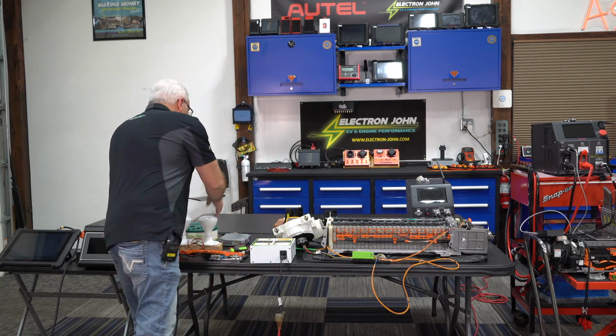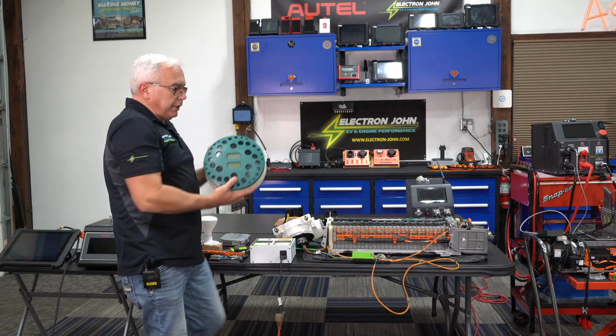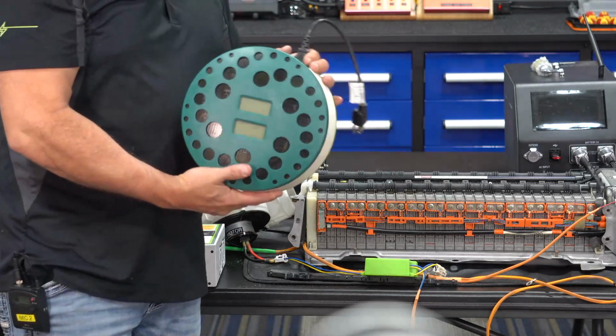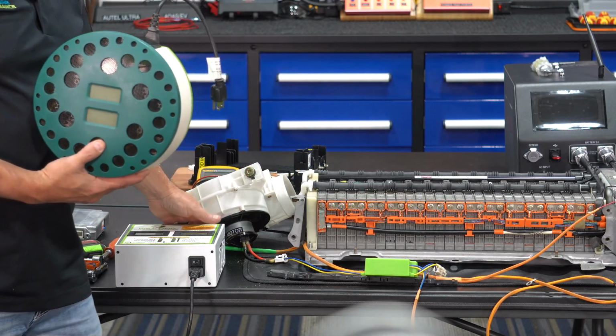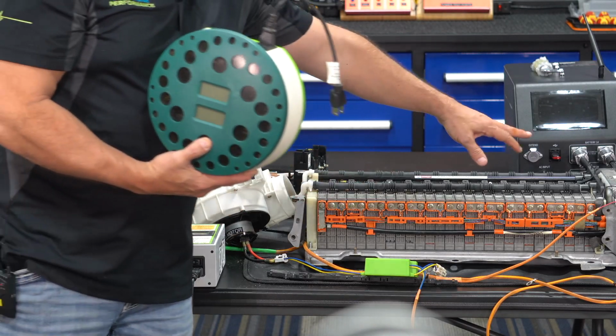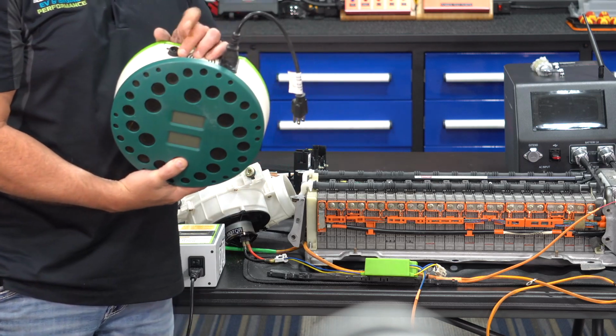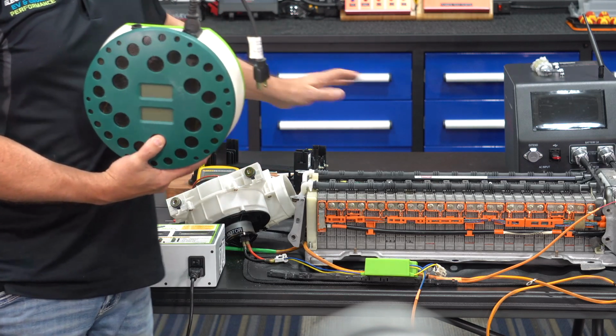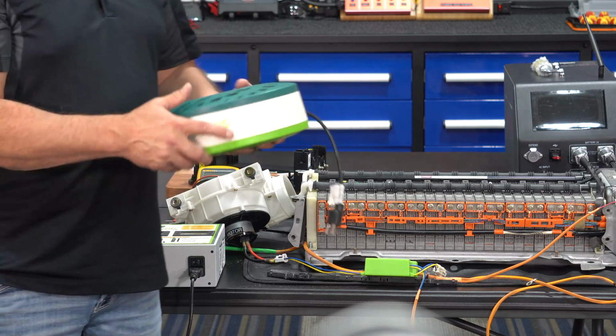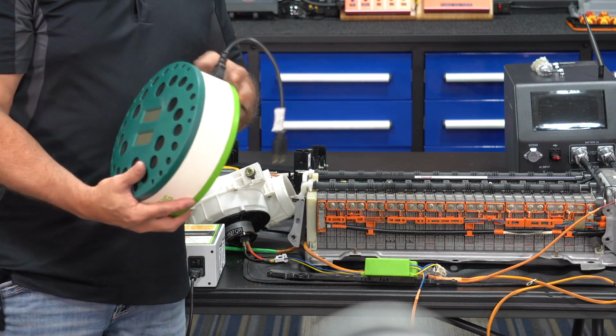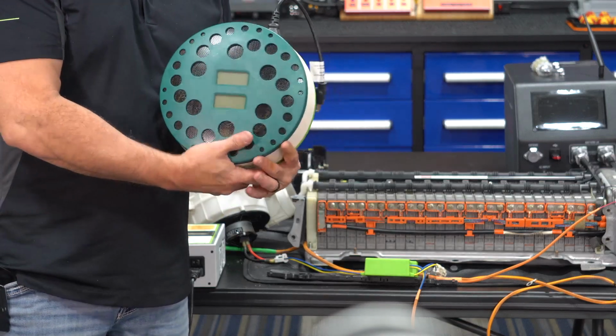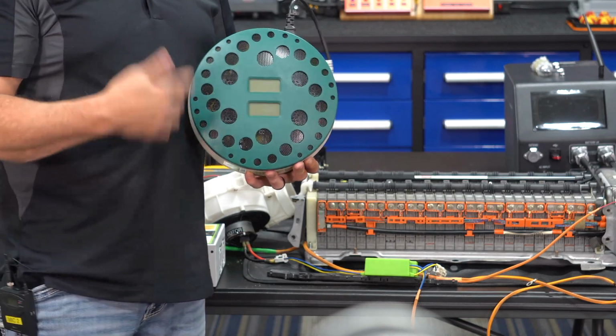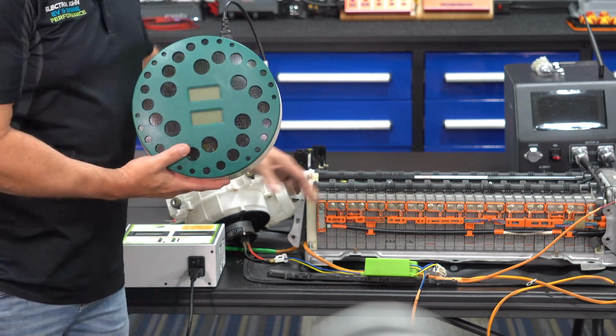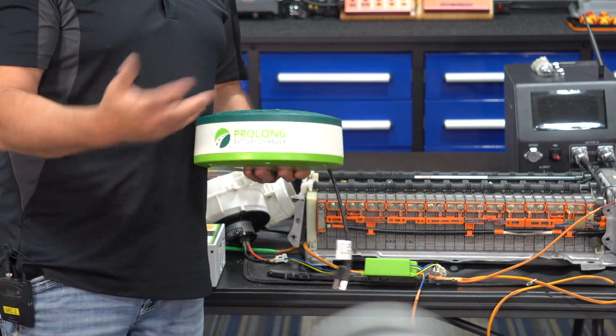Now with the Prolong units, that's a separate unit. This is another little charger that we would have. That same cable on the top that goes over to the contactors would just plug right into the top of this one, and it's also going to control the blower motor. Then I would just turn this one on, and it's going to balance the pack back up until the battery is fully charged, which is about 220 volts or so.